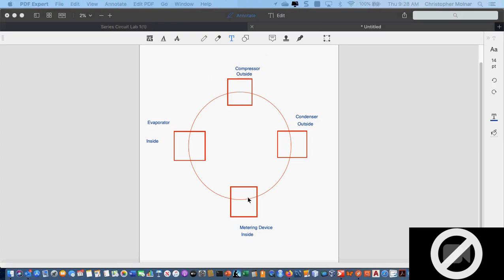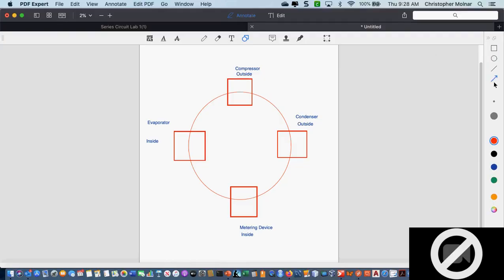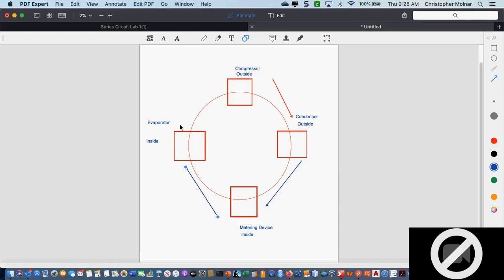This always works in the same order. This circle is basically the path of refrigerant flow. We come out of the compressor and go to the condenser. We come out of the condenser, we go to the metering device. We come out of the metering device, we go to the evaporator. We come out of the evaporator and go back to the compressor, starting the whole cycle over again.